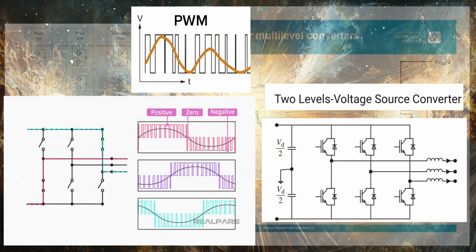Compare the MMC to a simple two-level VSC. For a converter of this scale, the switching IGBTs will chop up the DC power at various PWM intervals. This creates a choppy modulated AC signal that requires extensive filtering to remove the switching harmonics. Converters like these are perfectly suitable for low-voltage, low-power applications. The most expensive part of the converters are the IGBT semiconductors. As such, for small-scale applications, it's most cost-effective to rely on filtering.